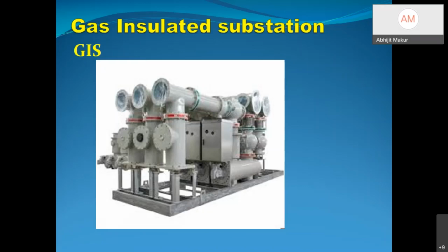GIS substations are now in vogue as land has become very costly, especially in the metros. For an AIS substation, the amount of land required is simply not possible to acquire. So since the technology has been found, GIS substations are now used by all utilities, from 400 kV downwards, and you can even use a GIS substation on a rooftop. So space is not a criterion. If you own a building, one floor can be used for the switchgear, and the remaining floors can be used for commercial apartments. That is the way we are moving ahead.